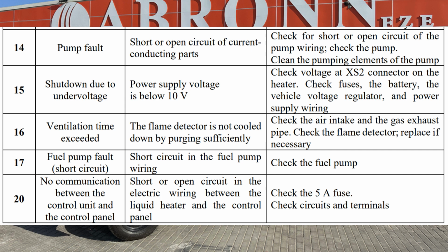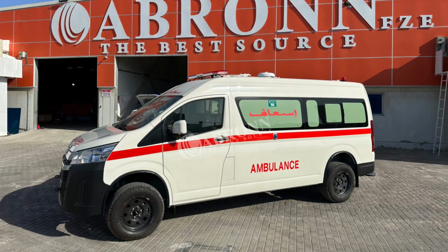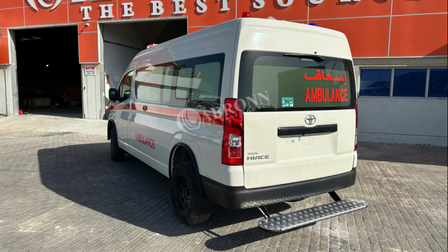It is important to remember that if the heater has not started after activation, the control unit will restart the heater in automatic mode. If the heater does not start after 2 attempts, a fault code will be displayed on the control panel. Look for the fault codes table in Section 6, Malfunctions, in this manual. For correct operation, the heater needs regular, annual maintenance.